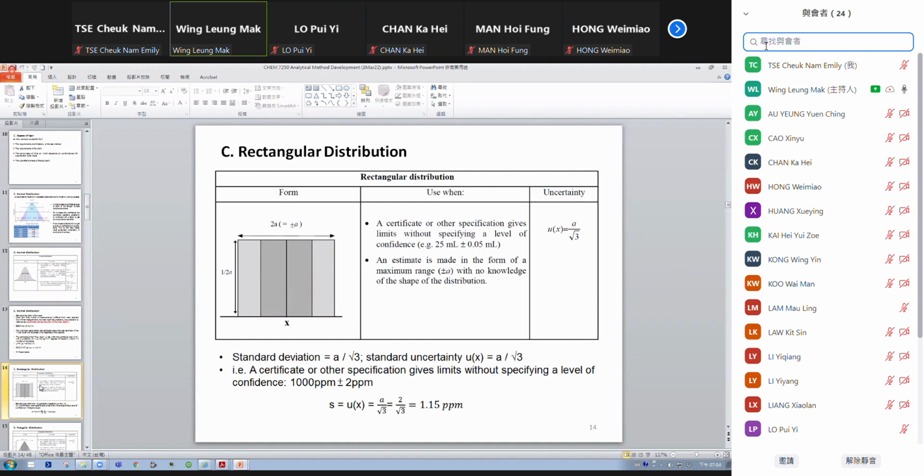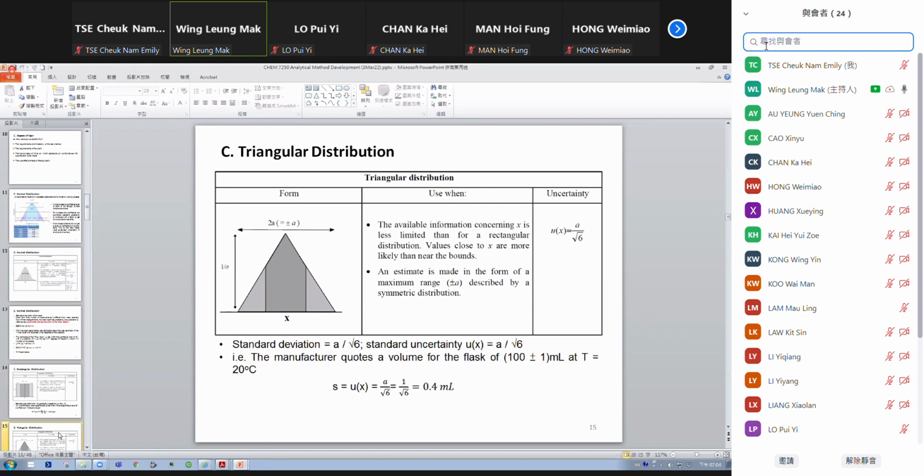And when considering that some experimental data, uncertainty data, cannot be covered by repeating, you may consider the distribution could be rectangular. Root 3 will be the factor for the calculations. Or maybe the distribution of that standard uncertainty will be in the triangular mode. Root 6 will be the factor for your calculations.